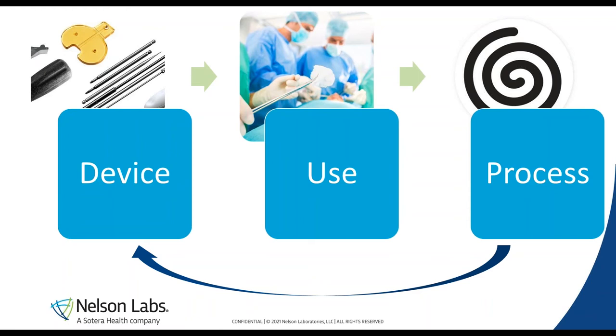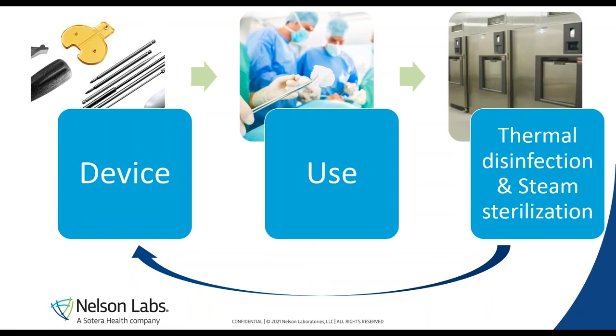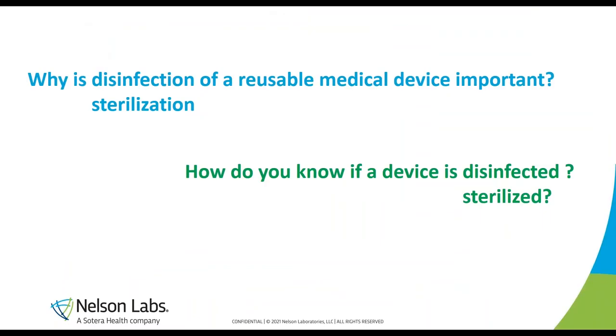Today we're only going to discuss two steps: thermal disinfection and steam sterilization. Steam sterilization is the last part of the processing cycle; thermal disinfection can also be the last part. Disinfection is important to reduce the amount of microorganisms present on the device from the previous use.